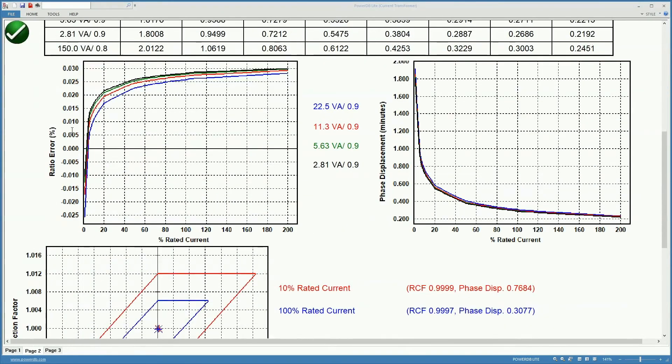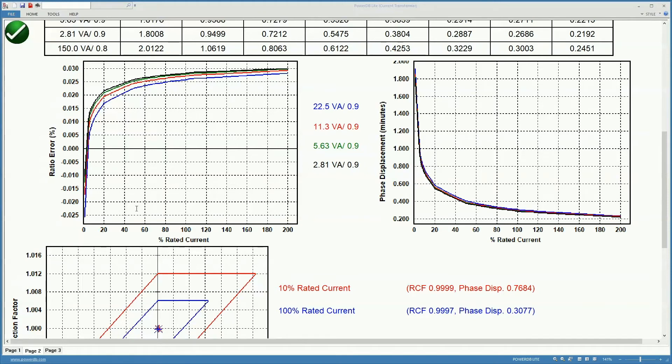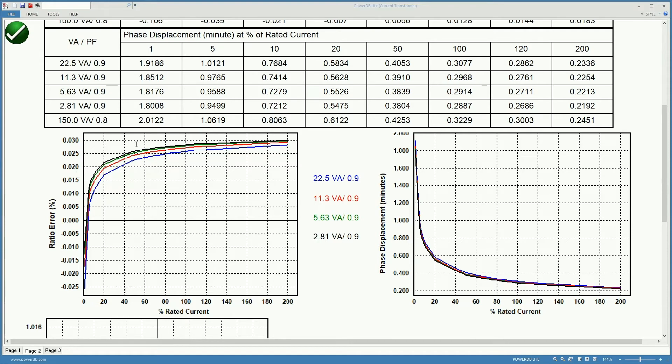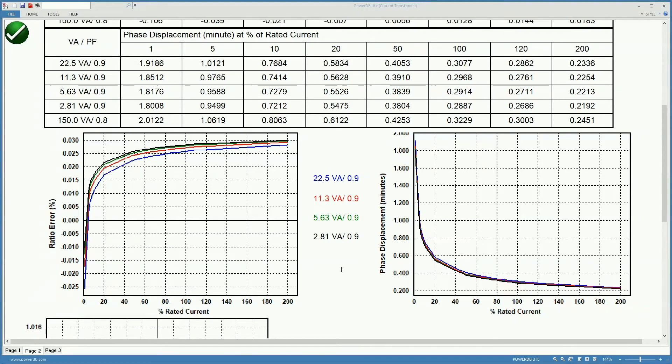Now here we have the ratio error in percentage at percentages of the rated current for different loads at a power factor of 0.9. You can use these curves in conjunction with electronic meters or relays to configure the correction factors that you can use in those instruments for the different percentages of rated current to make the accuracy of the measurements higher even when the CT is not absolutely accurate at all the different percentages of rated. On the right here you have the phase displacement in minutes as a percentage of rated current as well.